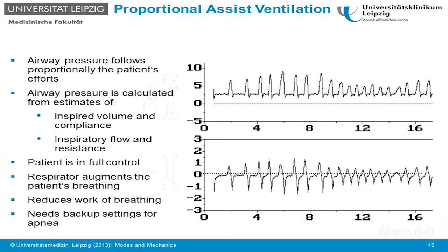Still not a very common mode to give the patient full control over all aspects of his ventilation is proportional assist ventilation, where the airway pressure follows proportionally to the patient's efforts. How does the machine determine the patient's effort? The machine has preset values for compliance and resistance of the patient. And from the amount of inspired air, the ventilator can then calculate the retraction force of the lung that has to be overcome. So if the patient takes a big breath, then we have a big retraction force of the lung, and the patient will need bigger help than when the patient takes a small breath.